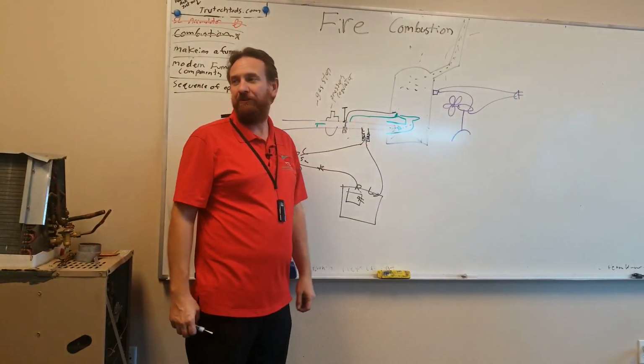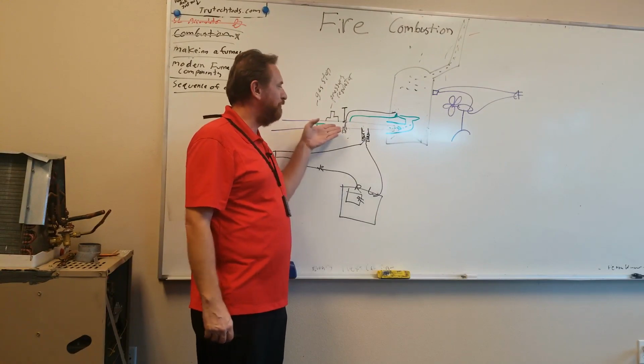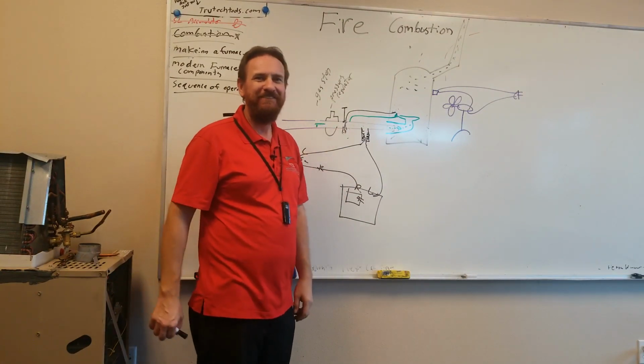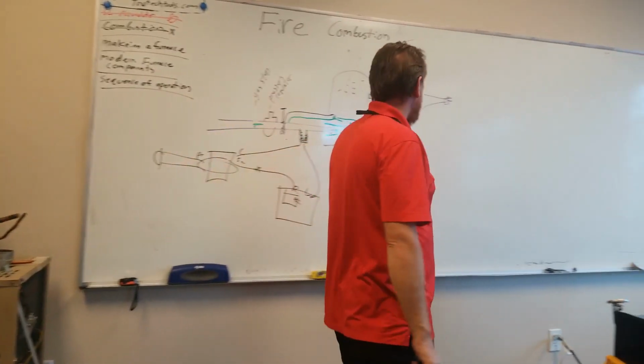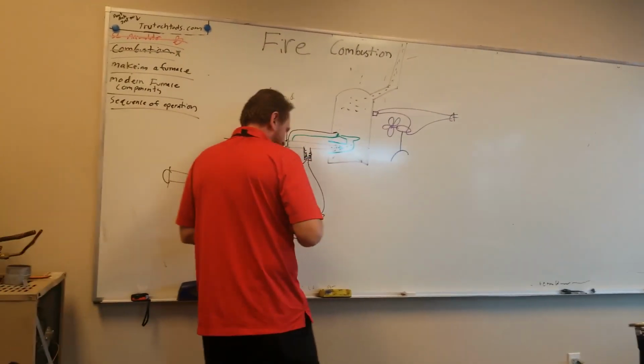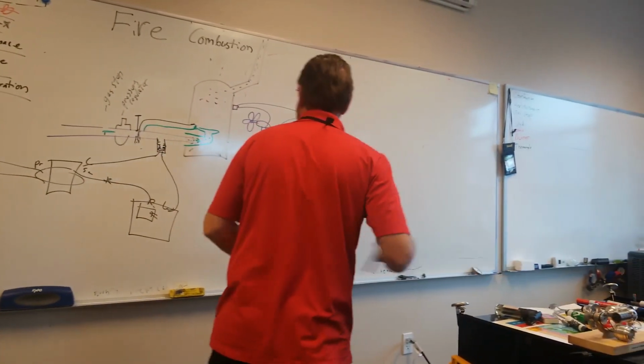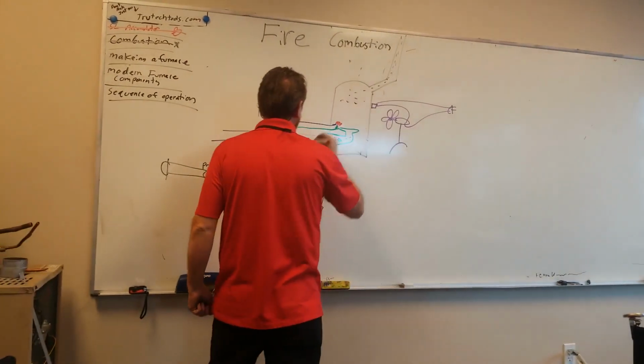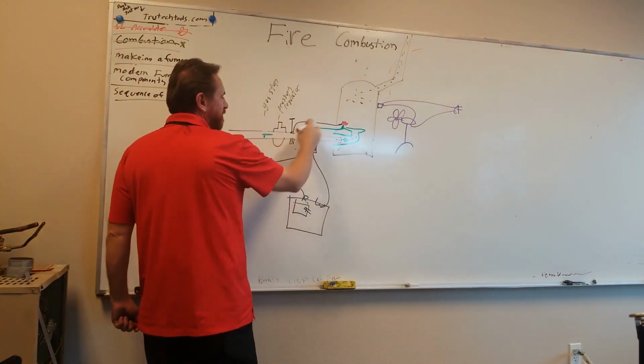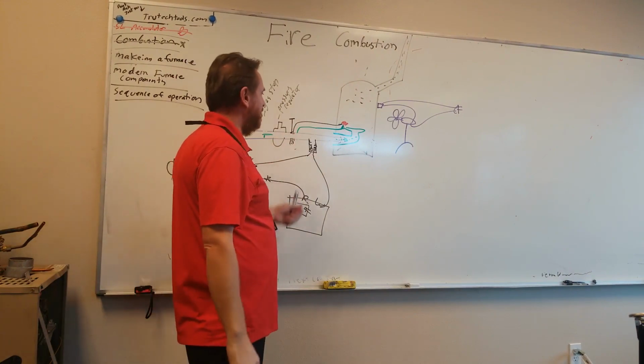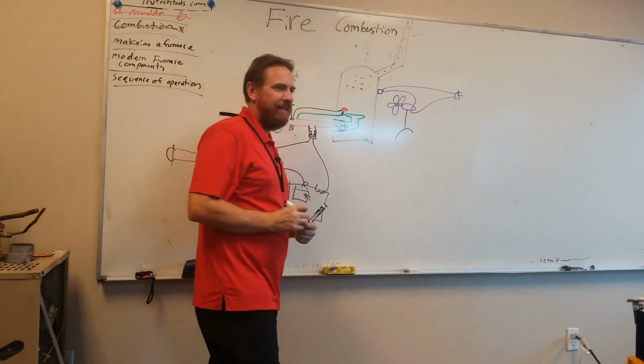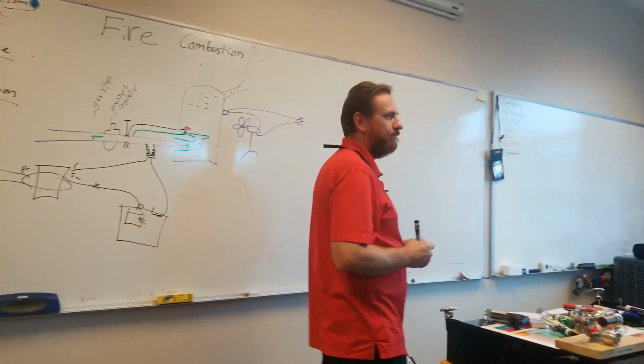Is there going to be any gas flowing? No, because it had to go through this one first. Pretty neat, huh? So I have to come back through, I press the button, I relight that little pilot valve. So I get my pilot valve lit. So I got my little flame burning. Right? I hold this, it stays open. I call for heating. This comes on, heats up, everything's running good, right?